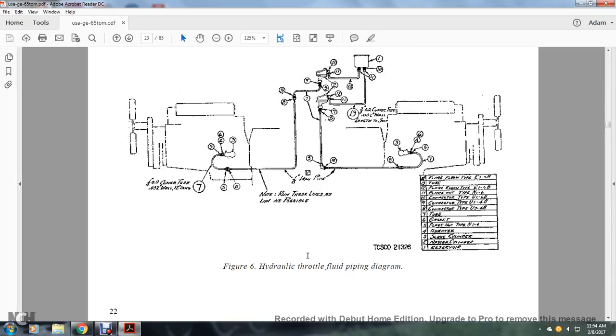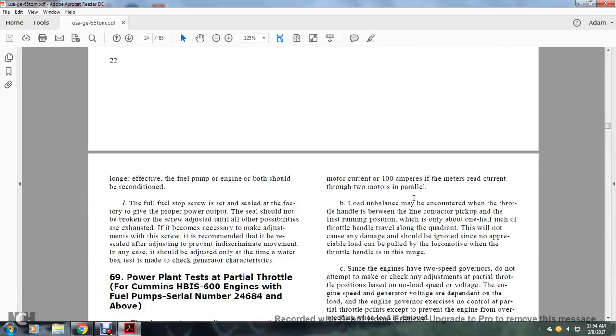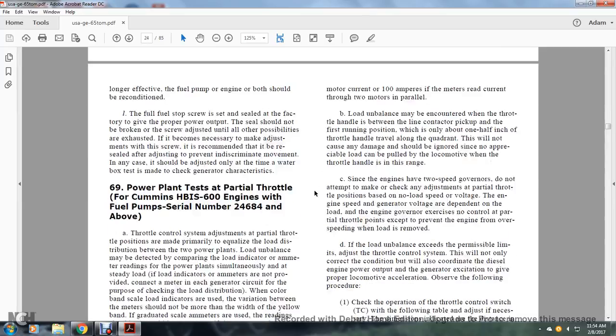Figure 6 shows the hydraulic throttle fluid piping diagram. If longer effective, the fuel pump or engine or both should be reconditioned. The fuel stop screw is set and sealed for a given power plant output and should not be adjusted unless other possibilities have been exhausted. If it is necessary to make adjustments to the screw, it is recommended to recheck and readjust after the adjustment to prevent any inadvertent movement. The test is to be made to check the generator characteristics.